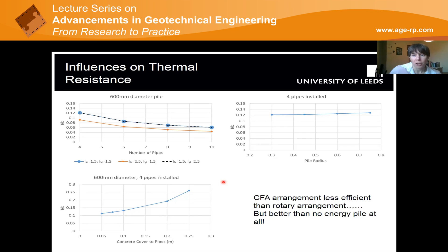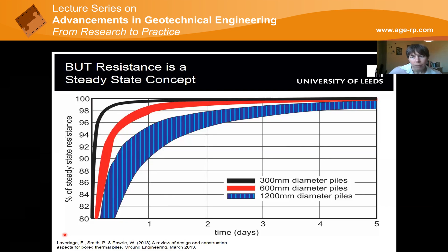The final important thing about resistance is that it's a steady state concept. This chart shows the percentage of that steady state achieved with time for a number of different pile geometries. You'll see it actually takes a number of days for a steady state to be approached in a pile. This matters because when you're operating the heating system of a building, the timescale on which thermal demand fluctuates is of the order of hours to half a day. You might turn your heating on in the morning and off at night. So your piles may be at 80 to 90 something percent of thermal steady state. One common design assumption is that the pile is at thermal steady state, but that's not actually technically true for energy piles. It's kind of getting there, but not totally, and that does have an impact on the thermal behavior, which I'll show as we go on.